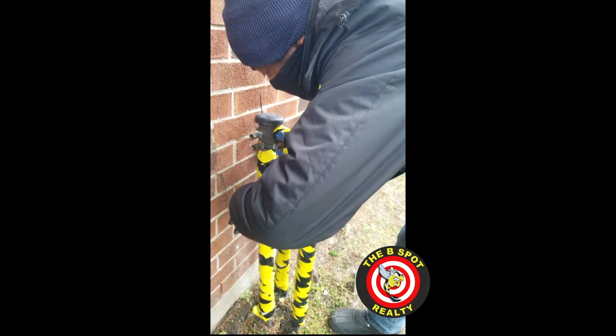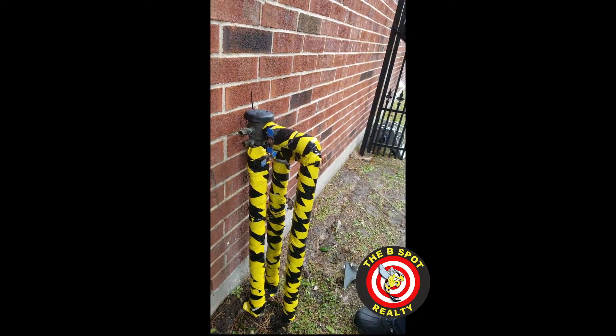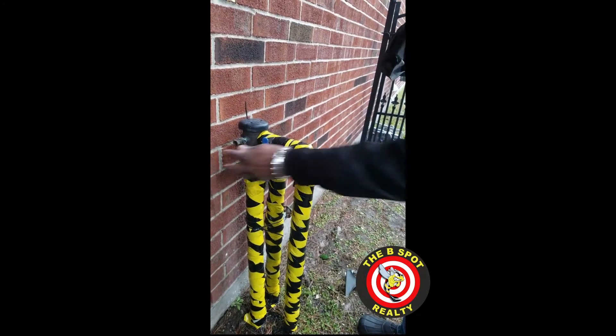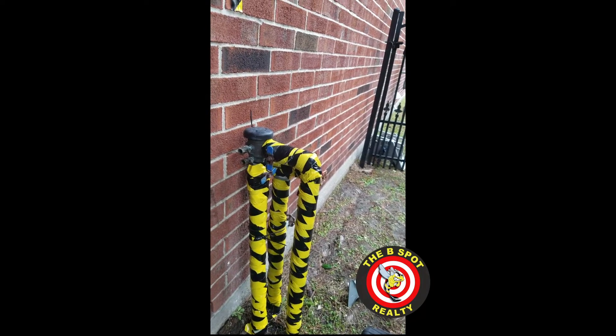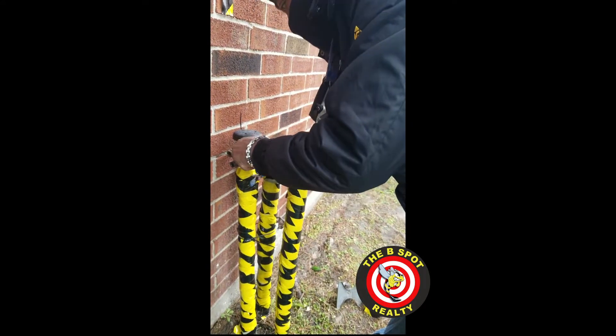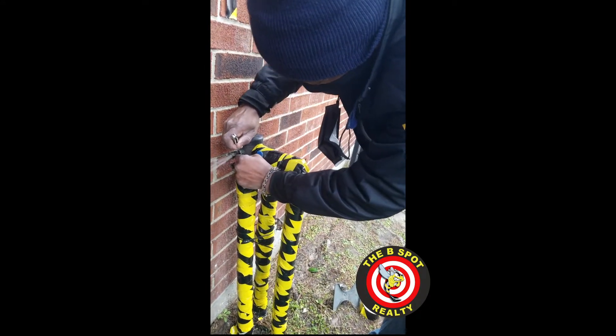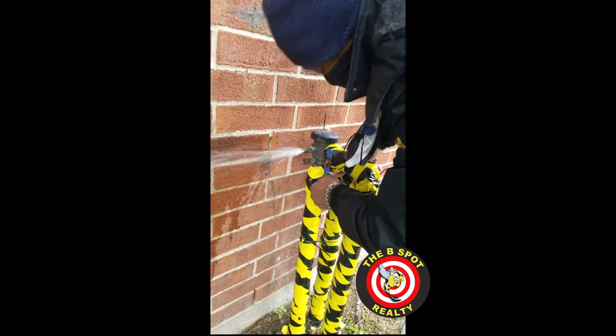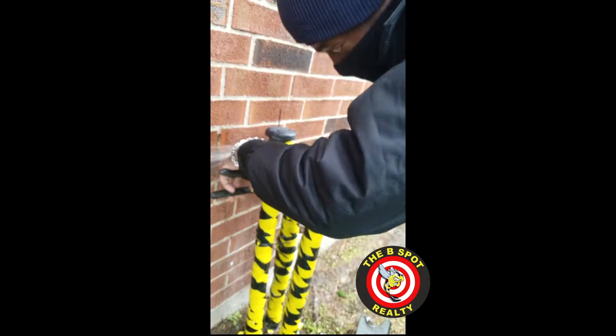After you do that, on some of them you have plastic caps right here — you want to take those plastic caps off. Then you want to open these bleeder screws right here a half a turn, and you'll see the water pressure come out. Some people use a flathead screwdriver. That's just the pressure from the line coming up.